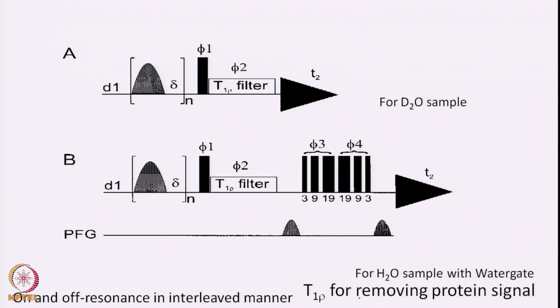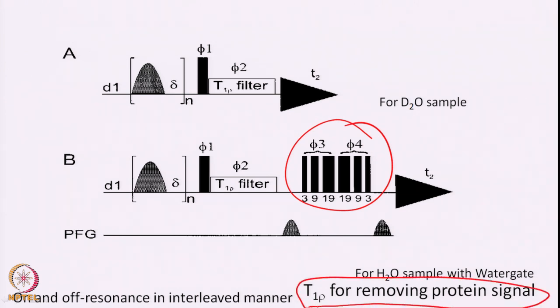The pulse sequence is done essentially in D2O to remove water background, though you can do it in H2O with water suppression (watergate). You need a T1-rho filter to remove the protein signal. The experiment is simple: saturation, then a 90-degree pulse, then T1-rho filter for removing protein signal, then detection. You increase the saturation time by increasing N. You do two experiments - on-resonance and off-resonance - in an interleaved manner and subtract them to save time. As you keep increasing saturation, more and more peaks will be affected, telling you the group binding epitope.